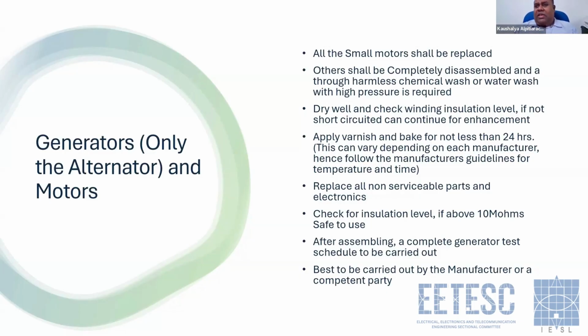With the insulation results you are getting, you can assess whether we are proceeding with a rewinding or enhancing the insulation. Let's say you're getting 500 kilo ohms, 1 mega ohm. Yes, you can refurbish. If it is short circuited, 0, then most probably you will have to rewind.